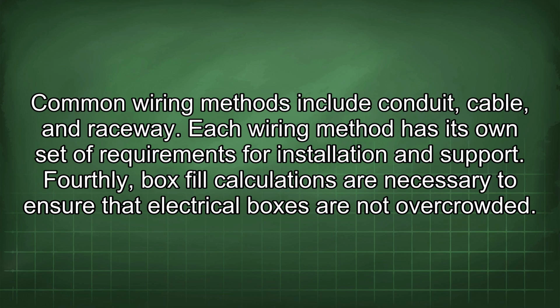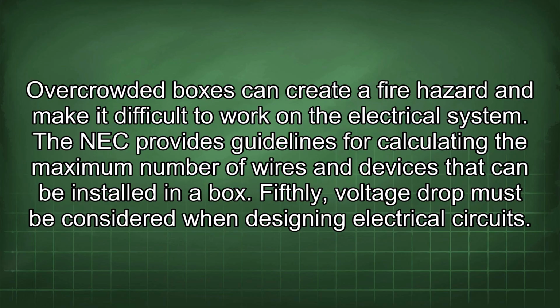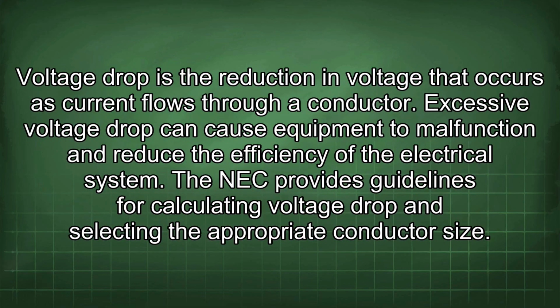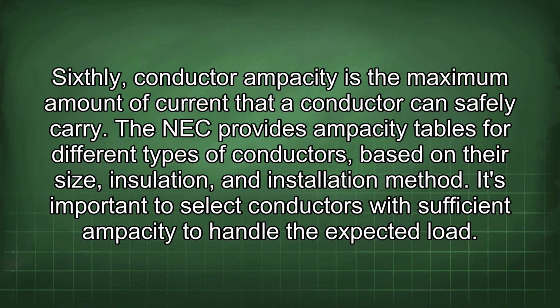Fourthly, box fill calculations are necessary to ensure that electrical boxes are not overcrowded. Overcrowded boxes can create a fire hazard and make it difficult to work on the electrical system. The NEC provides guidelines for calculating the maximum number of wires and devices that can be installed in a box. Fifthly, voltage drop must be considered when designing electrical circuits. Voltage drop is the reduction in voltage that occurs as current flows through a conductor. Excessive voltage drop can cause equipment to malfunction and reduce the efficiency of the electrical system. The NEC provides guidelines for calculating voltage drop and selecting the appropriate conductor size. Sixthly, conductor ampacity is the maximum amount of current that a conductor can safely carry.